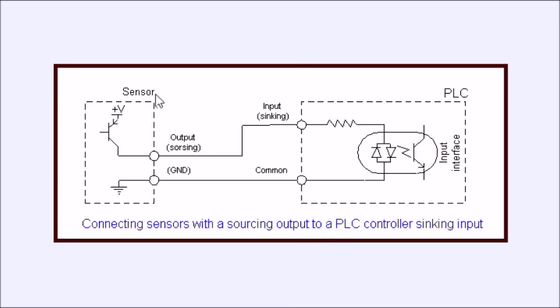Let's look at the source configuration. Your current loop is usually completed through the sensor. In this case the sensor will switch on. It connects the positive side of the circuit which again goes through the PLC's optocoupler and associated circuits back to ground. But because I'm using these back to back LED emitters I'm not really worried about polarity. It doesn't care which way the source current is going to move. It just cares that it's there. So this is a sourcing input. Your positive side of your circuit is going to come through the sensor to the optocoupler and return to ground.